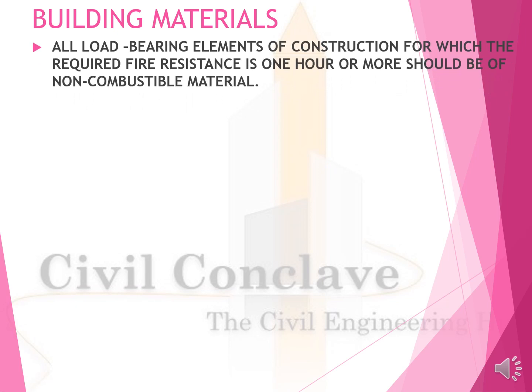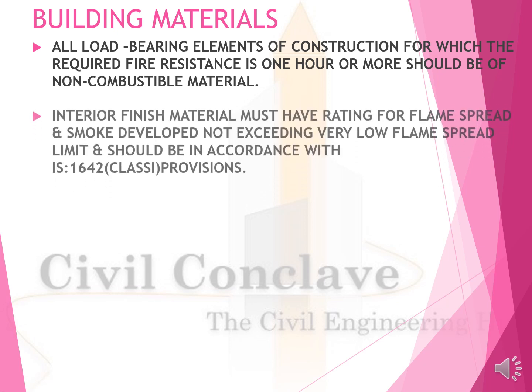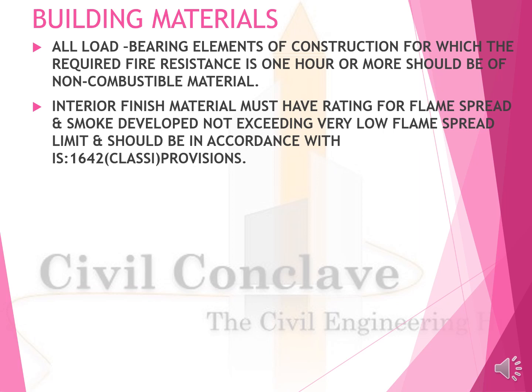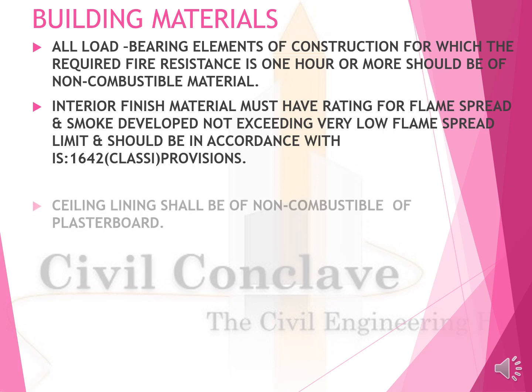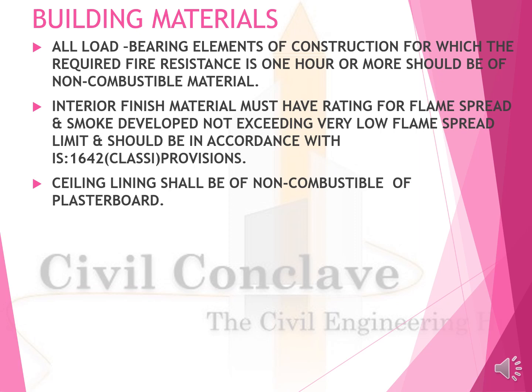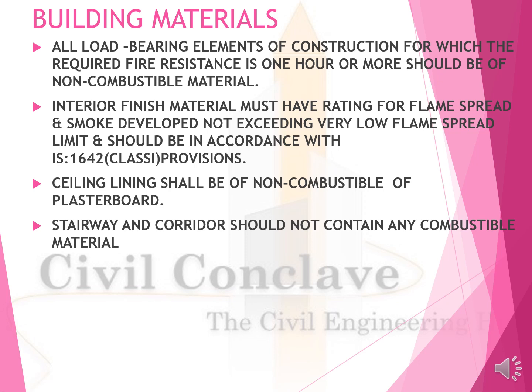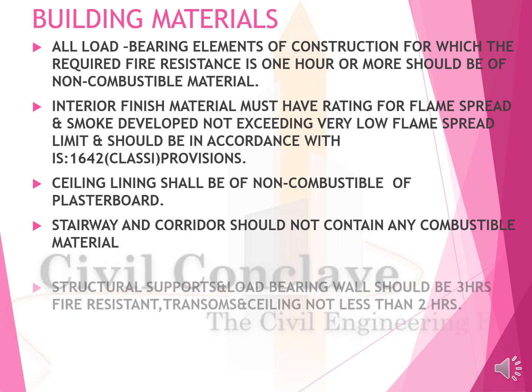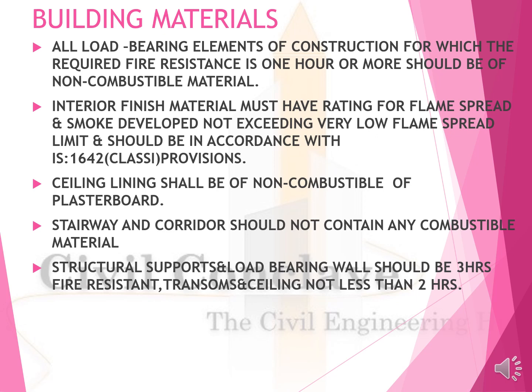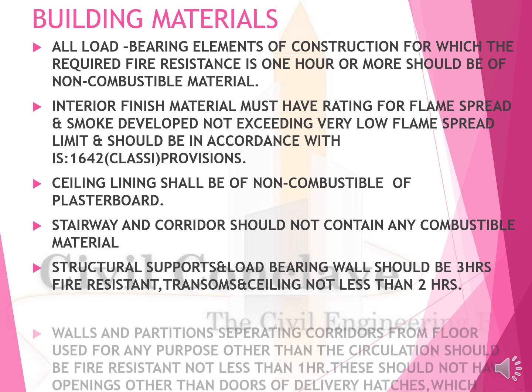Building materials. All load-bearing elements of construction for which the required fire resistance is 1 hour or more should be non-combustible material. Interior finishing material should have a rating for flame spread and smoke developed not exceeding the low spread limit and should be in accordance with IS 1642 provisions. Ceiling lining shall be a non-combustible material. Stairway and corridor should not contain any combustible material. Structural support load-bearing walls should have 3 hours fire resistance and floor ceilings not less than 2 hours.